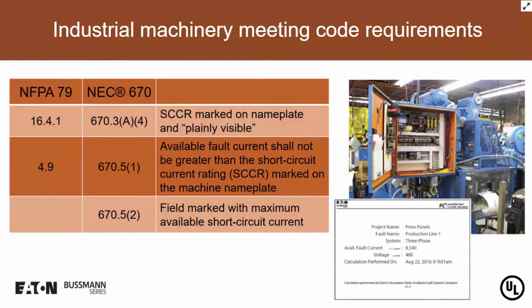There is a little bit of difference, and that is the location of the nameplate. In NFPA 79, the nameplate shall be provided on the outside of the industrial control panel or the machinery, whereas the NEC Article 670 is silent on that, and it uses the term plainly visible. I can tell you that plainly visible is not defined in either the NEC or NFPA 79. It's a term that's certainly been discussed at length by the NFPA 79 committee, trying to define what that means so that it's clear to enforcers and certainly users of the document what the requirement is, how to interpret it.